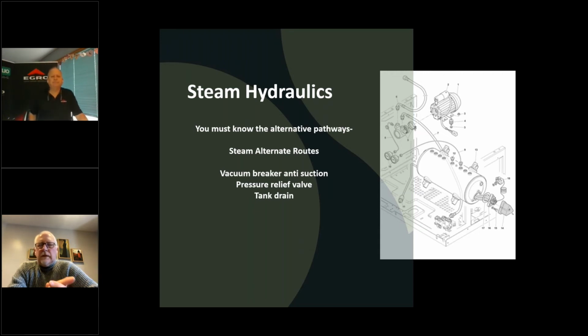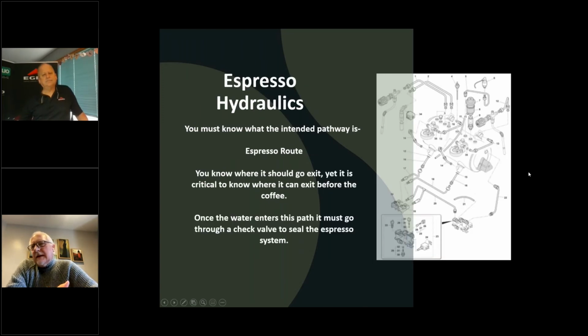Michael? No, that's exactly right. When you have a vacuum in a tank, it's like having 1 bar of pressure on the outside of the tank, and it wants to suck water or something from everywhere. If you've got a home machine, it'll suck it from the reservoir. If you don't, and you open up a steam valve and it's cold, you'll suck the milk right into the boiler. So yeah, the vacuum valve does two functions.